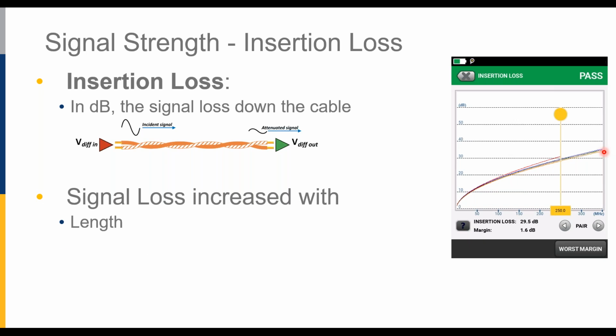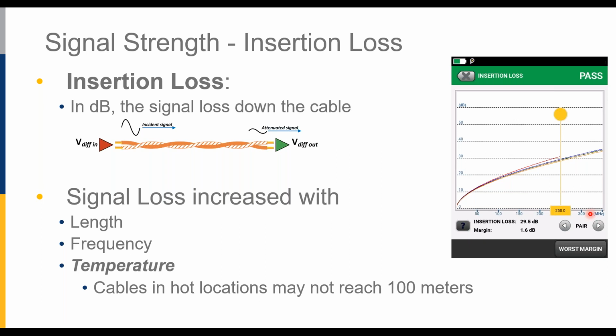So in addition to increasing with length, it also increases with frequency. You'll notice it's going up and to the right. Our horizontal scale is the frequency in megahertz. At higher frequencies, we're going to have more signal loss. And something that kicks in in industrial environments, signal loss also increases with temperature. So you need to be careful to understand what the temperature is going to be in the environment that you're operating in while you're operating there.